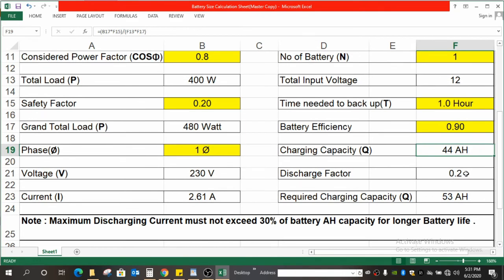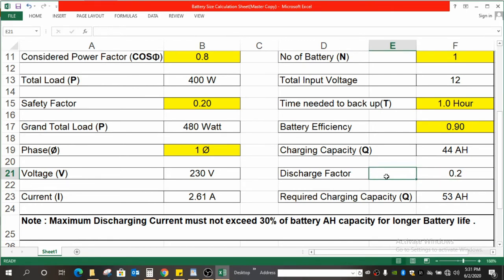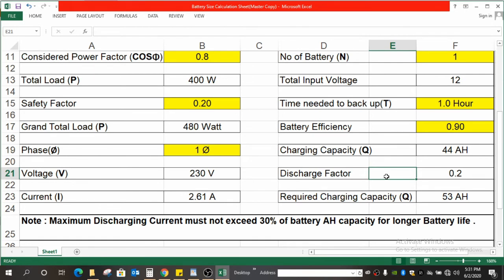One more thing we have considered over here is the discharge factor. This thing is considered actually on the safer side. If you don't need it, you may not. Let me first explain what discharge factor is. In a battery, if the capacity is 44 Ah, in no case should the battery be drained totally—44 Ah at a time. As per the manufacturer's advice, the battery should keep 20 to 30 percent. It varies from manufacturer to manufacturer. Otherwise it will affect the battery life.